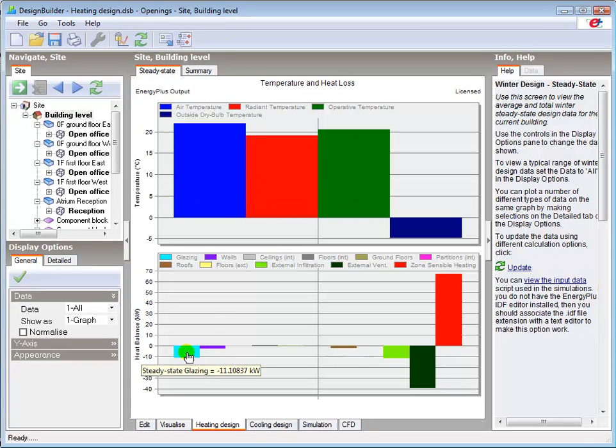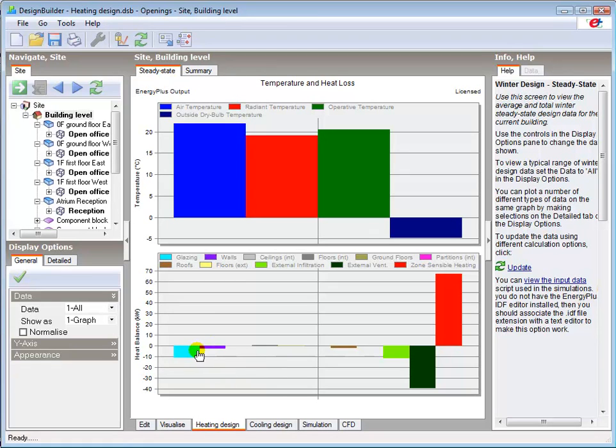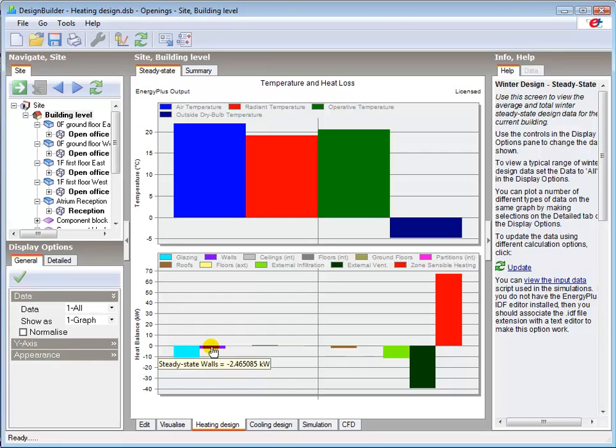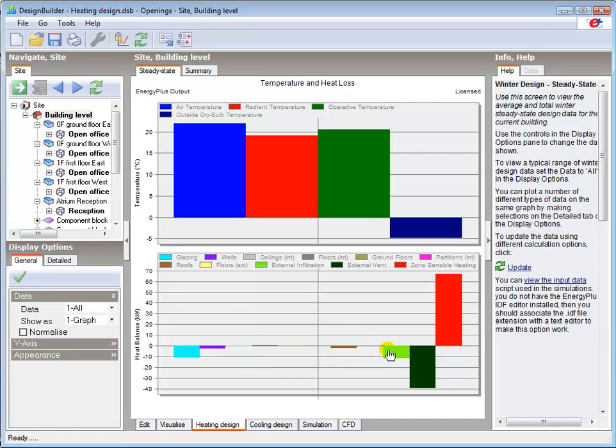The losses from the glazing and the walls have reduced by around a third and a quarter respectively to 11.1 and 2.47 kilowatts. And the infiltration losses have reduced by more than half to 11.73 kilowatts.